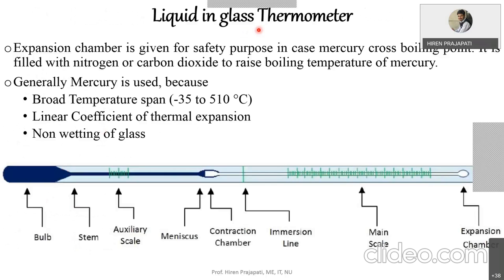For the liquid-in-glass thermometer, the bulb portion is the sensing point which makes contact with the hot medium. The stem is the main body, and we have a scale on it. The immersion line is the line up to which we need to dip the thermometer in the hot medium. We also have a linear scale and an expansion chamber at the end.